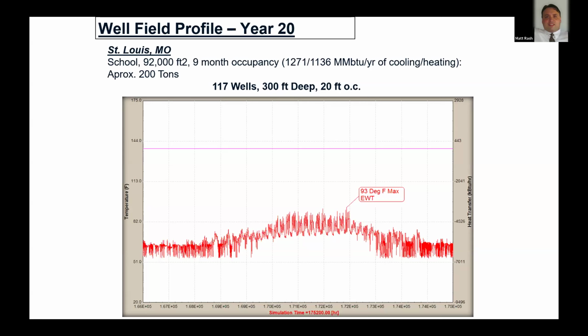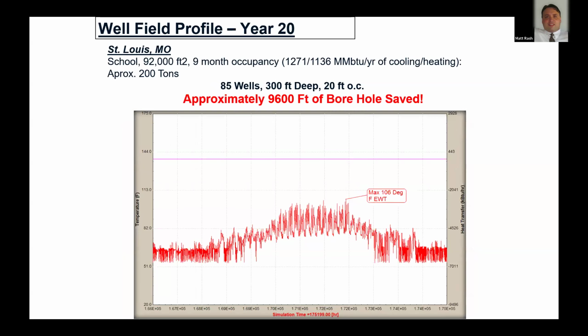So here's an example with a 20-year well field profile simulation, on year 20, for a school in St. Louis. You can see that if the 20-year peak temperature was limited in this design to around 93 degrees, you have 117 wells, 300 feet deep, 20 foot on center. That's typically how a lot of these well fields are designed, to not exceed a 20-year limit temperature. If you can allow that to bump up to 106 degrees, you can reduce that to 85 wells. So that's close to 9,600 feet of borehole savings.